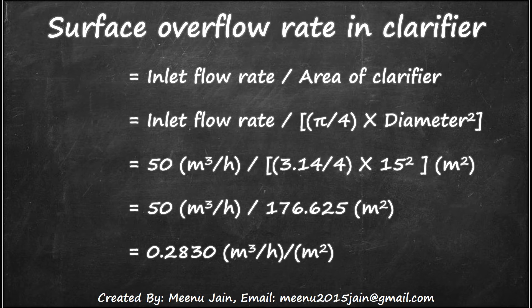That is inlet flow rate divided by (π/4) multiplied by diameter squared, i.e. 50 meter cube per hour divided by 176.625 meter square, which equals 0.2830 meter cube per hour per meter square. So this is the surface overflow rate in the clarifier.